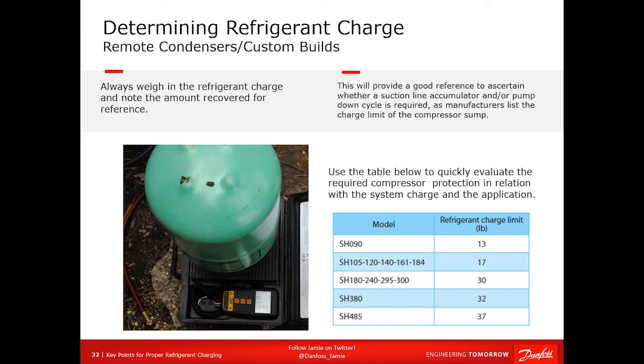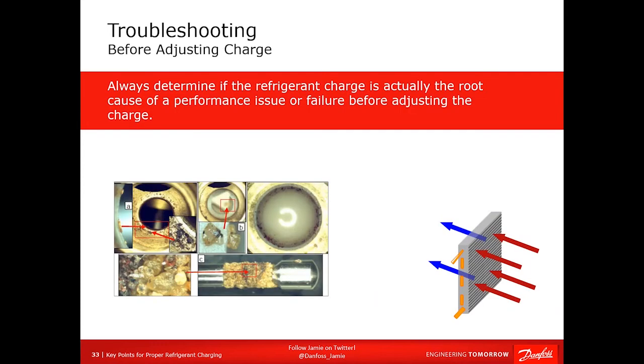Weigh in that charge to know exactly how much you put in. You should have documentation — a worksheet — whether you're doing startup, commissioning, troubleshooting, service work, or PM. Put all this information in there. If something goes wrong down the road, you have proof that you did what you were supposed to. If somebody claims the system was never charged correctly, you show them the refrigerant charge you put in, the subcooling values you measured, and so on. That documentation is your evidence — I have had to use it and it saved me. It also guarantees the system is charged correctly.